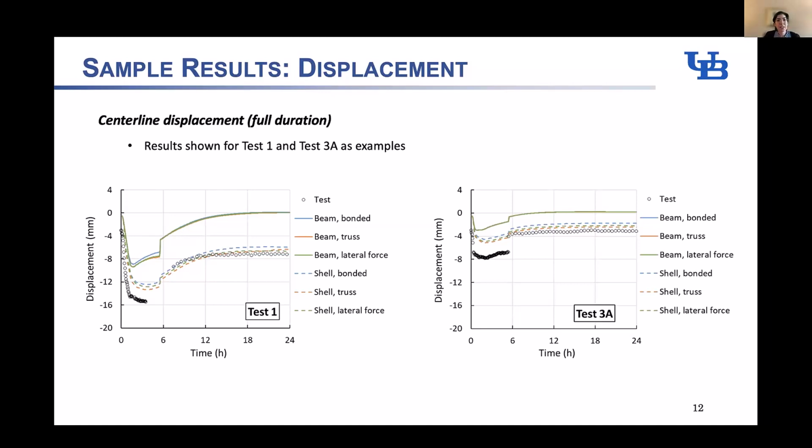But we were very happy with the way that the shell elements worked. To be exact, this kind of model is actually not too bad, I need to be honest. The mechanical model for shell elements ran for 2 hours. That's it. So they're actually pretty efficient. Our recommendation was that shell elements perform really well in heating and cooling and provide good predictions. So that's the way to go.